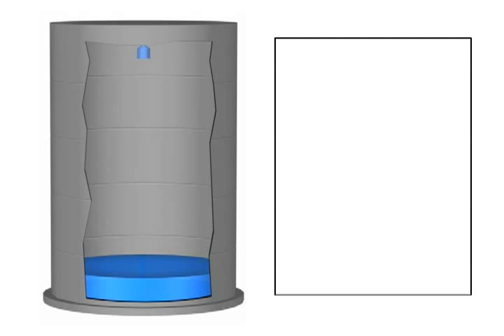The ultrasonic transducer emits high frequency pulse. This pulse travels down to the liquid level. When the echo strikes the liquid surface, it is reflected back up to the transducer. During this time, the ultrasonic device is listening for the reflected echo. This is shown in the graph window.